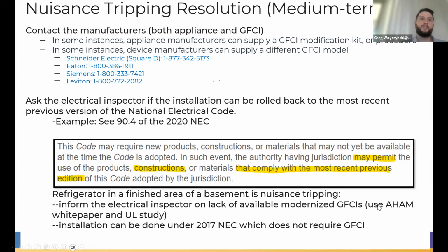So you can hand the electrical inspector our white paper and the UL study and say, listen, there are new products that are not yet available, new GFCIs that are not yet available. So in those cases, we can go back to the most recent previous version of the code. Because the current version of the code is the 2020 NEC in our example, we can roll back to the 2017 NEC, an older version of the code that does not require a GFCI on this installation. So I know that's not the fastest solution. You have to get a hold of your local electrical inspector, but this is something the code allows, and you can get in touch with them to get permission to do this.